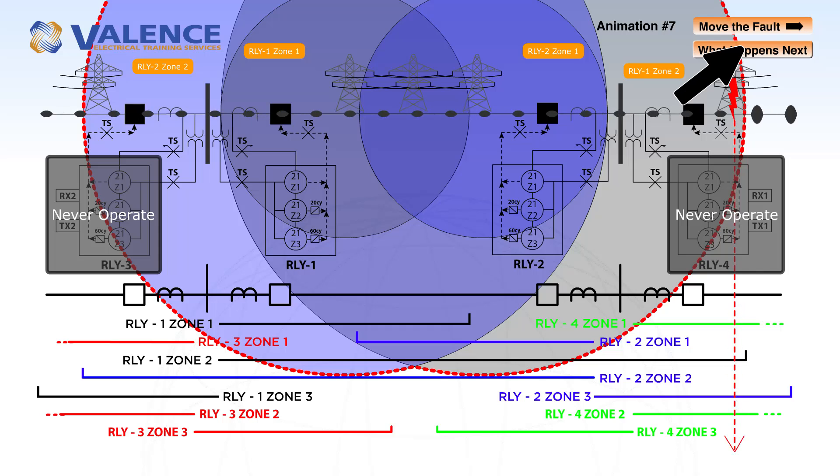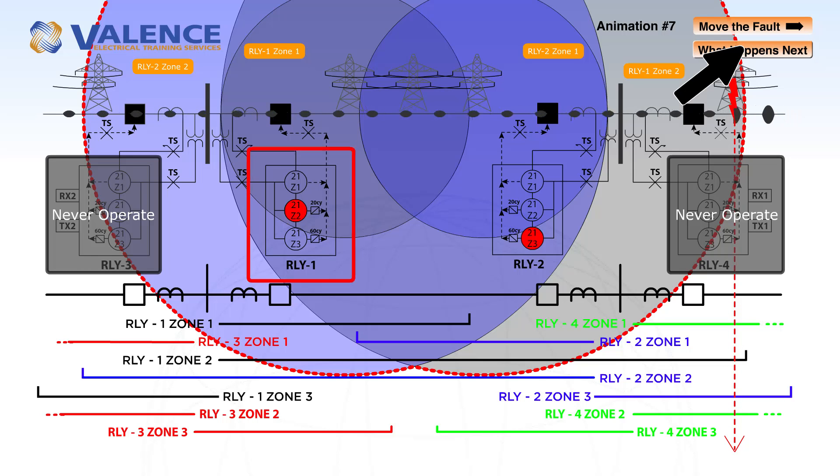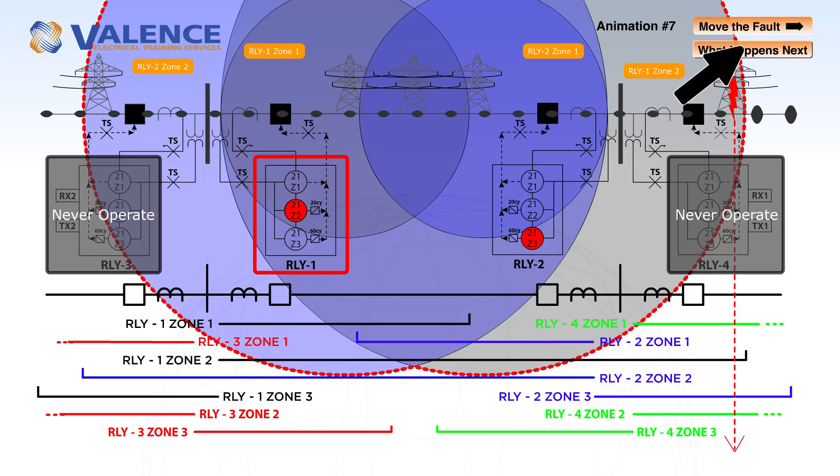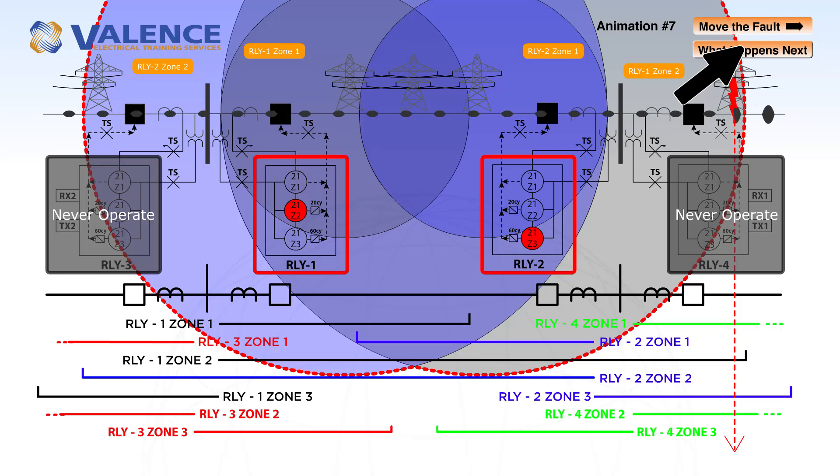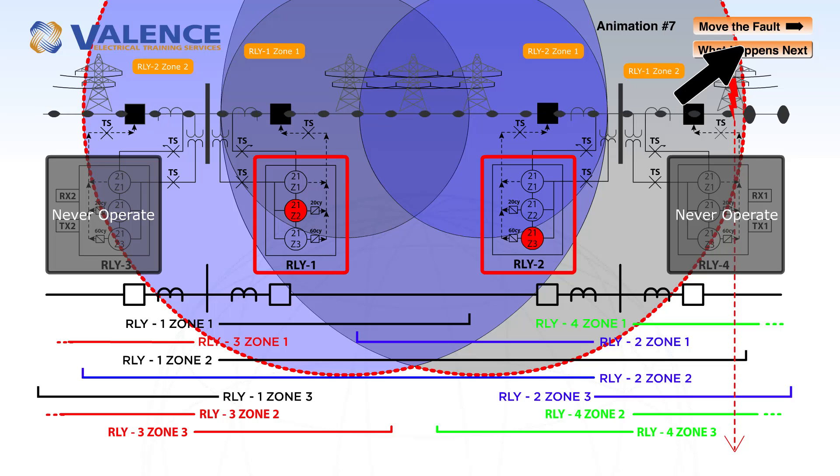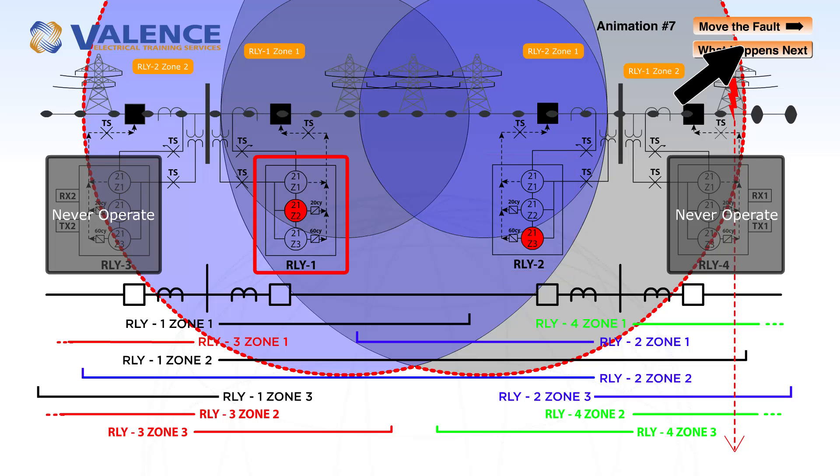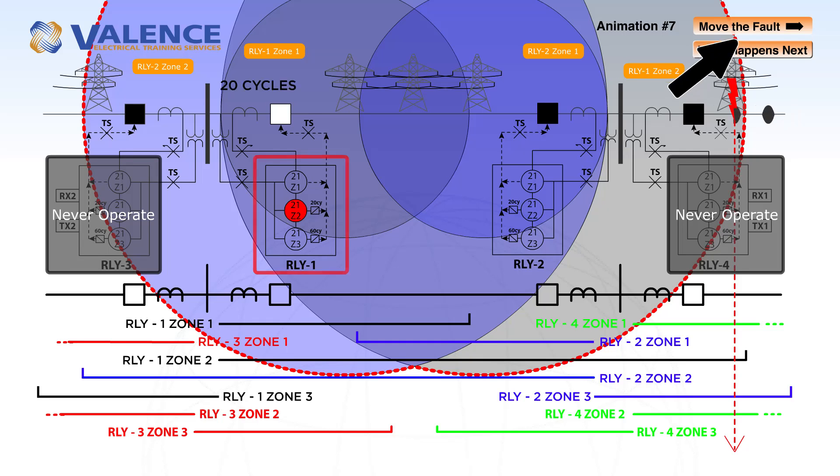If we move to the other side of the line, you can see that the opposite happens. Zone 2 on relay 1 is going to pick up, and zone 3 on relay 2 will also pick up. Zone 2 has a smaller time delay, so the breaker connected to relay 1 is going to operate first.